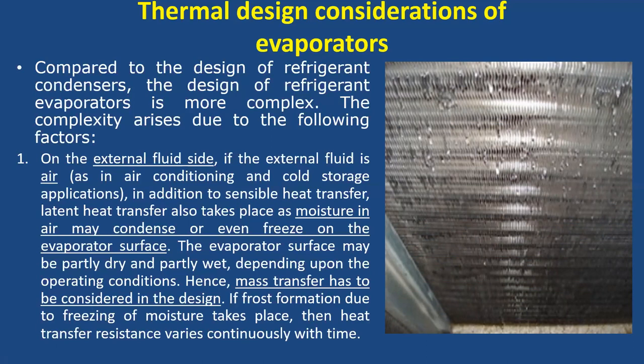So that is only sensible heat. If your air loses some water vapors, so water vapor condenses. Like this, you can see the droplets of water, wet coil. In that case, that is because of the conversion of vapor to liquid. So some latent heat also needs to be considered, and that part is also considered during the design.